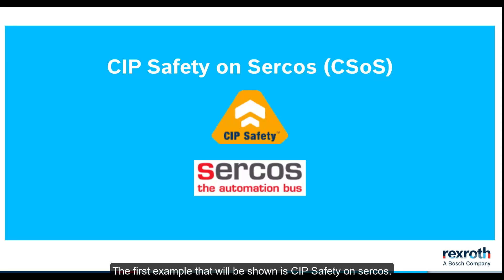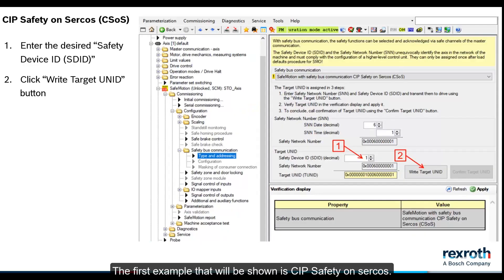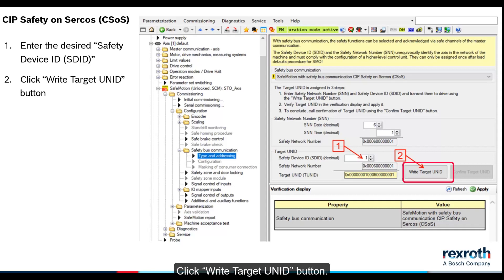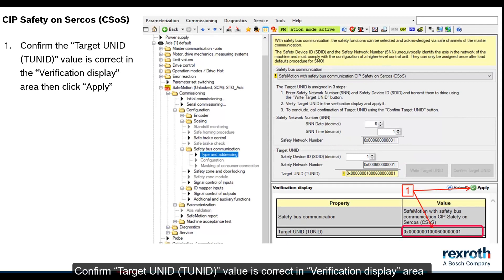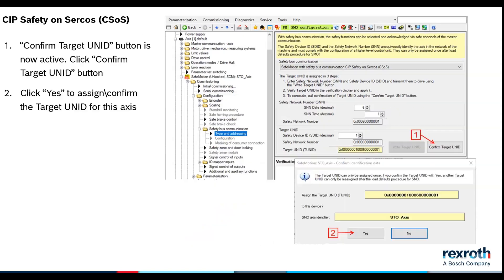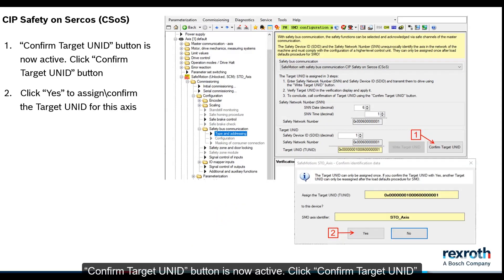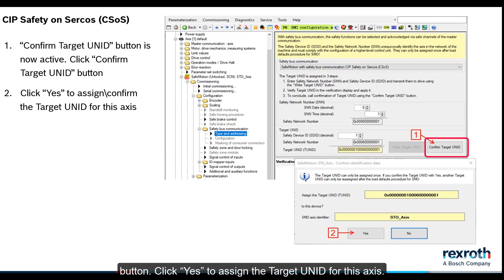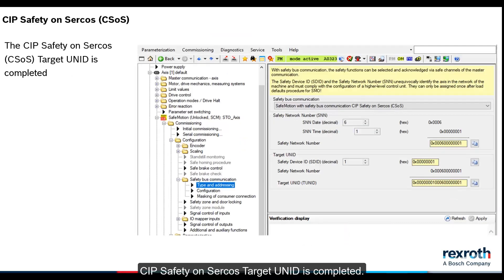The first example that will be shown is CIP Safety on Sercos. Enter the desired safety device ID SDID. Click write target UNID button. Confirm target UNID value is correct in the verification display area, then click apply. Confirm target UNID button is now active. Click confirm target UNID button. Click yes to assign the target UNID for this axis. CIP Safety on Sercos target UNID is completed.